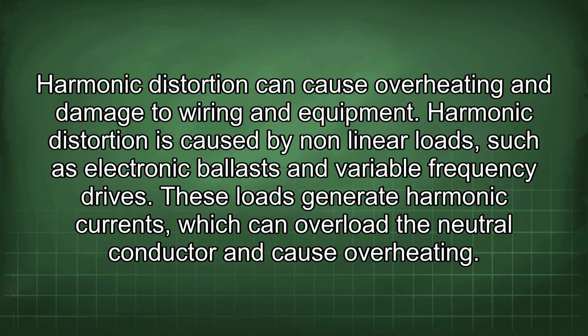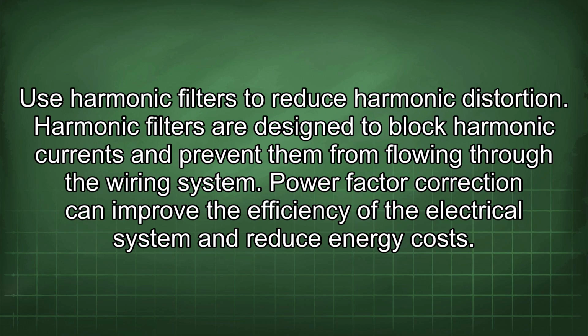Harmonic distortion can cause overheating and damage to wiring and equipment. Harmonic distortion is caused by nonlinear loads such as electronic ballasts and variable frequency drives. These loads generate harmonic currents, which can overload the neutral conductor and cause overheating. Use harmonic filters to reduce harmonic distortion. Harmonic filters are designed to block harmonic currents and prevent them from flowing through the wiring system.